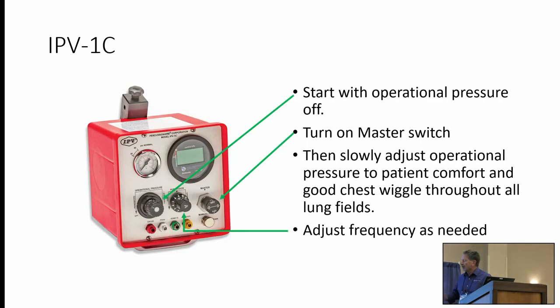Just to go quickly over the two devices - you would start with the 1C, as it's called. It's actually called the operational pressure, but that's what you're going to turn up. It shows in a dial as PSI, but that's not what's going to the patient - it's just the pressure coming into the device. It's giving the pressure in centimeters. You turn on a master switch, then slowly adjust your operational pressure.